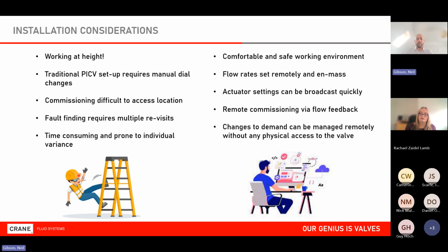So we can reduce the number of these ladder events quite significantly. We don't have to do any of the manual dial setup on the PICVs. It's all done remotely now. Often, this is one of the biggest issues when we're working in hard to reach locations. And to give an example of the Cat B fit out, all too often I've come across a fairly new building and they've completely concealed access to any of the valves or equipment. You just can't access them.